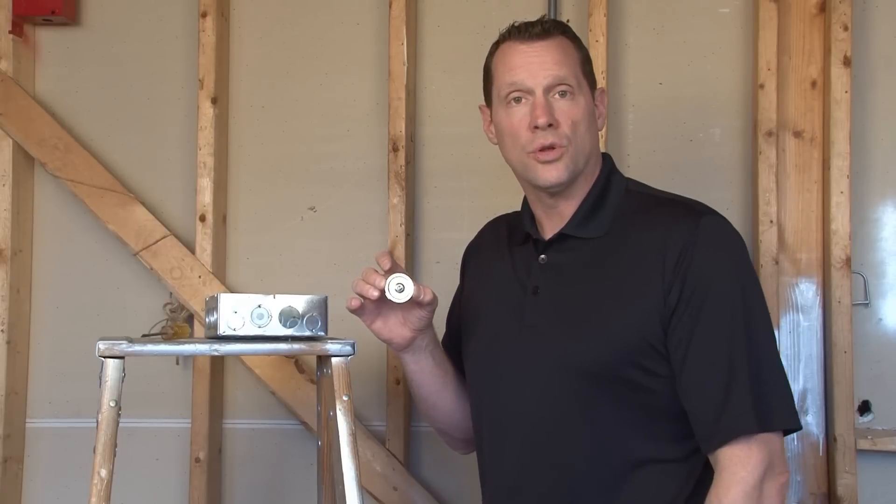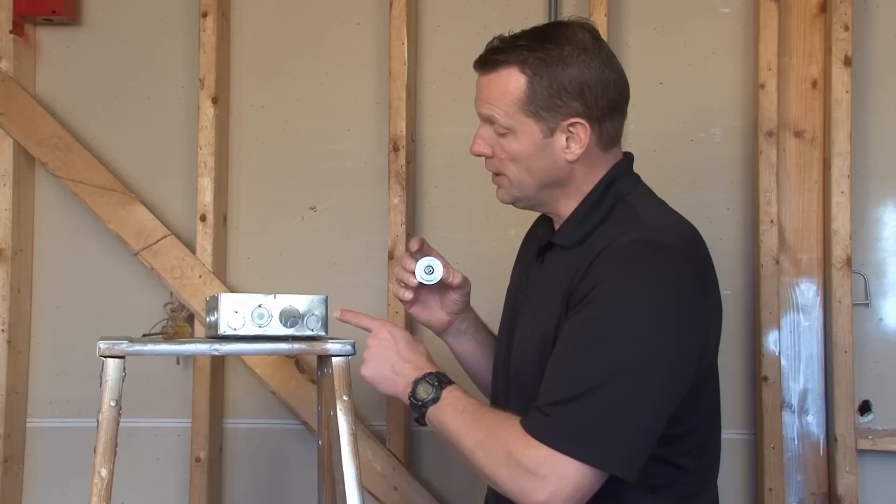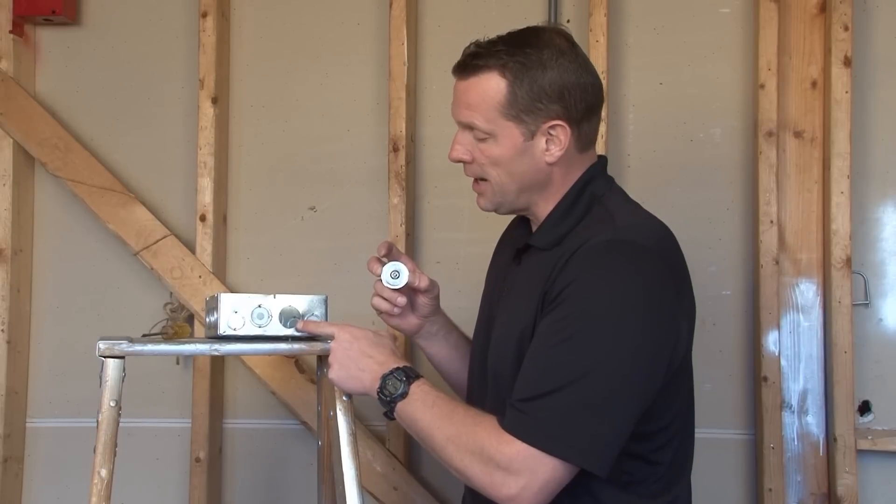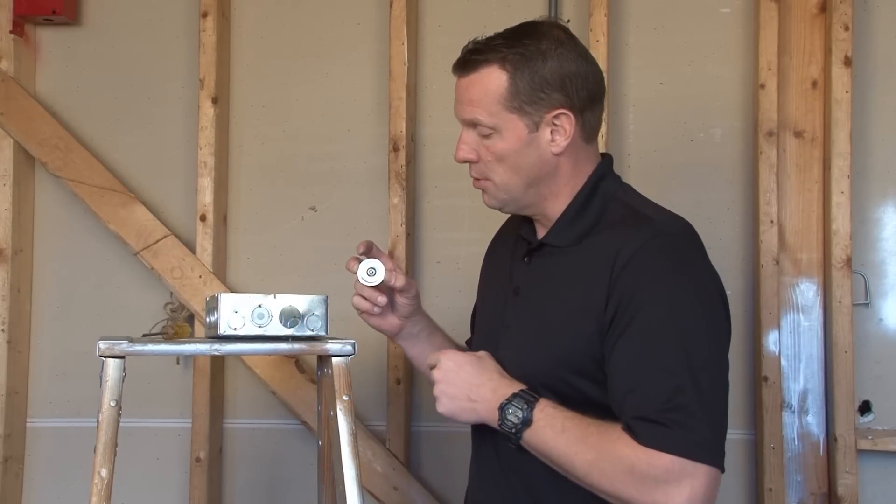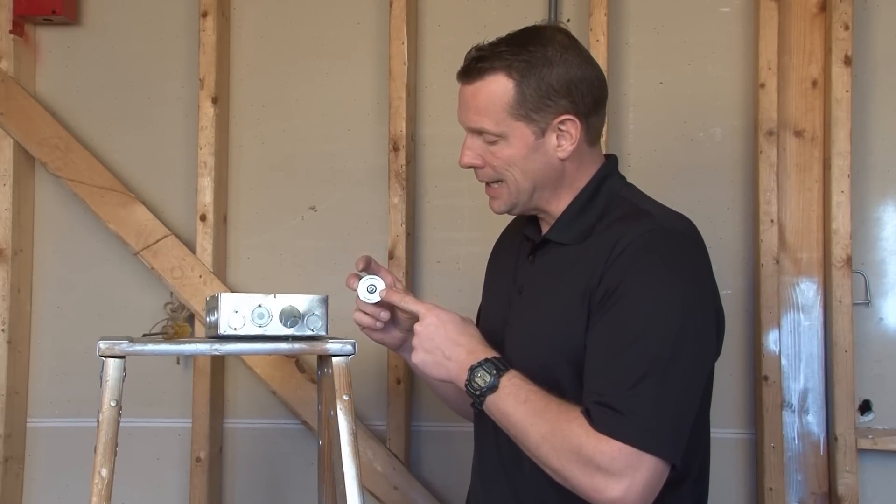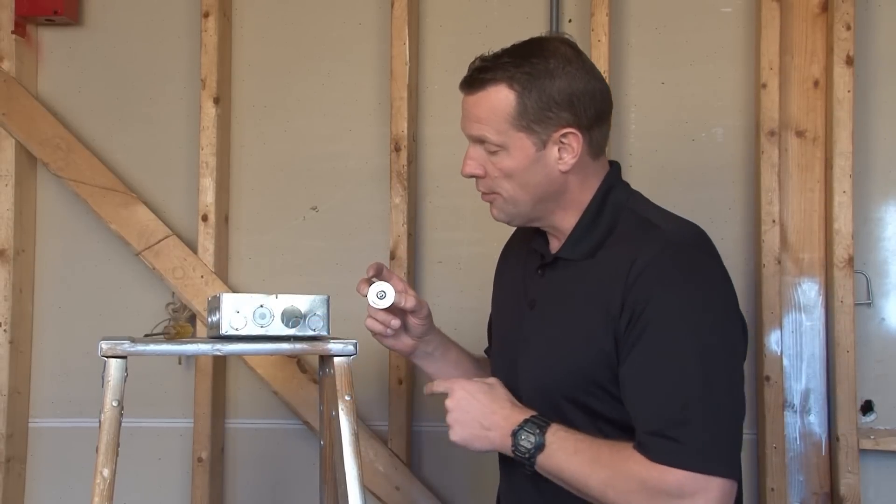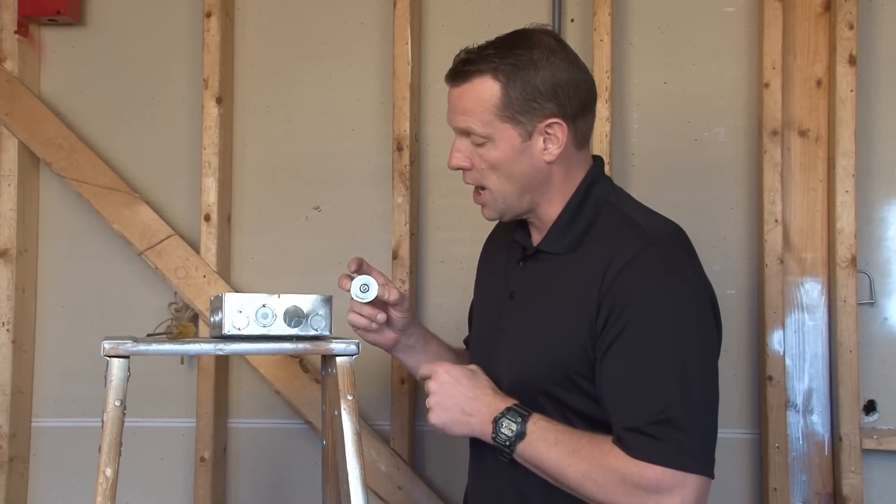Many times when installing electrical conduit, an installer will leave an open knockout by mistake. This is a violation of the National Electrical Code and requires a knockout seal to be installed in the open hole, preventing risk of electrical shock.